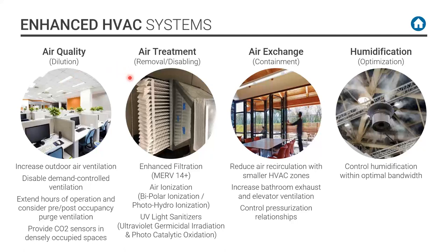Okay, and how do you remove a contaminant? If it gets back to the air handling system, you put in good filters. And there's different types of filters we'll go through. We're talking about enhanced filtration. ASHRAE is saying MERV 13. We're suggesting 14 or better.